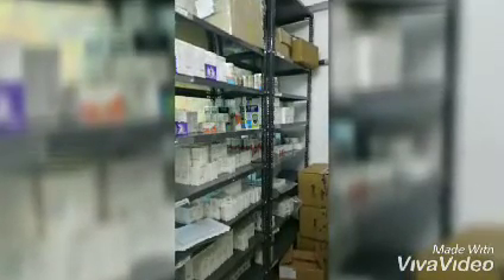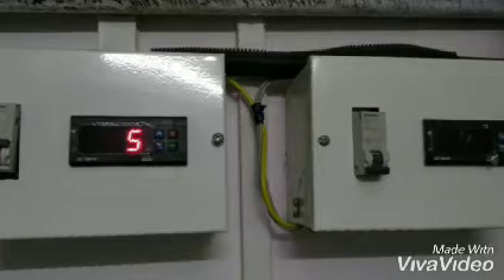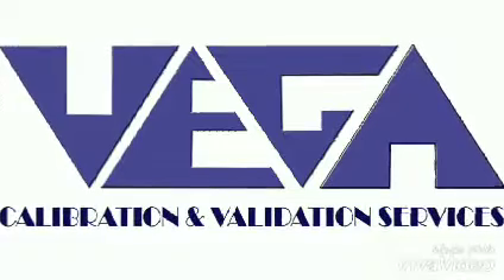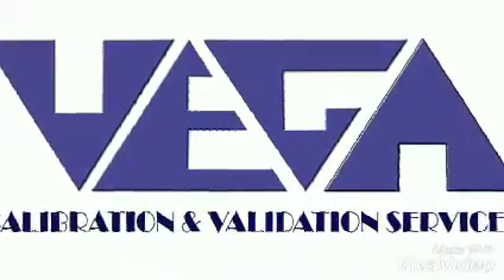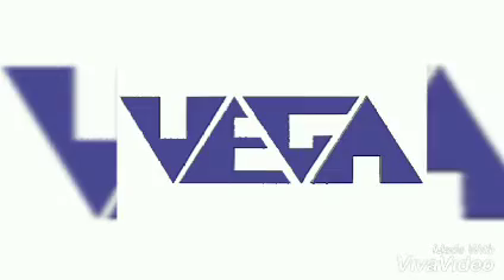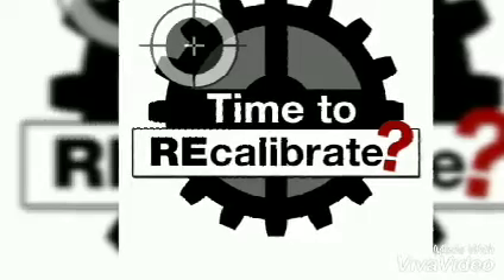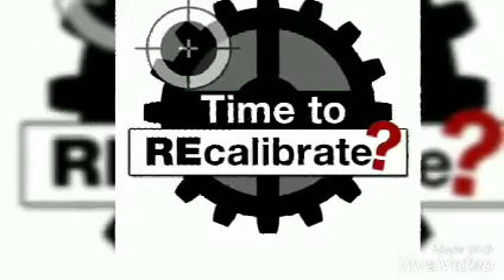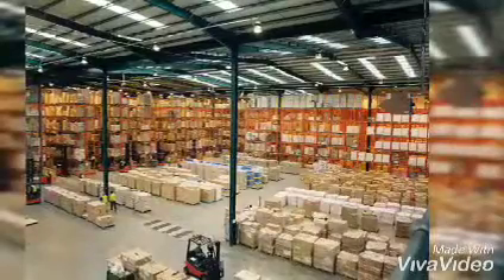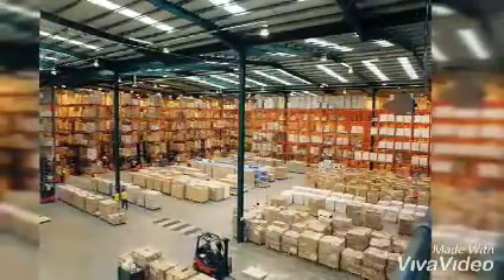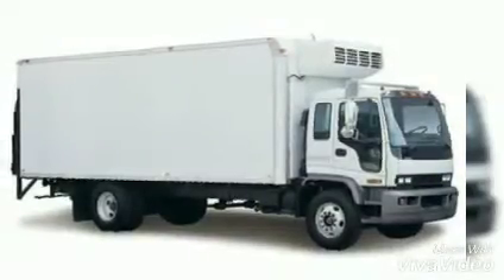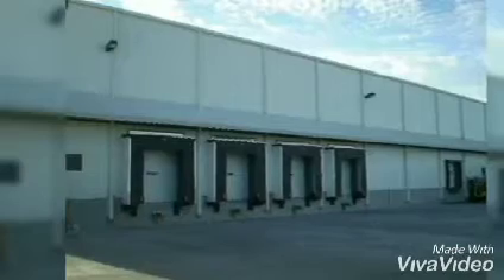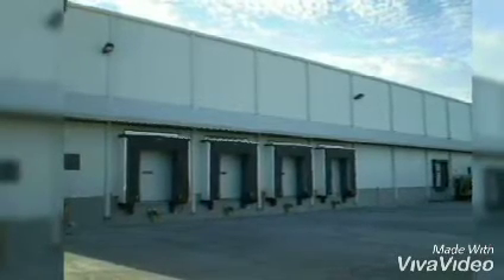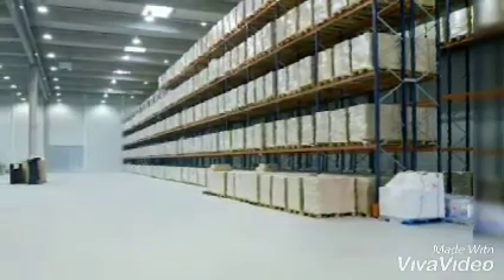So now, let us understand how VEGA performs the mapping study for its clients. The mapping study starts with a primary inspection of the area where the temperature mapping study is to be performed, and deciding the number of loggers and positions of the loggers. Once this is finalized, our VEGA engineers start with the mounting of the wireless temperature data loggers at the defined positions. Once the loggers are mounted, we start with the operational qualification study. This continuous cycle test study is to be carried out for 24 hours, 3 days or 7 days depending upon the client protocol. The operational qualification study cycle is also known as the empty cycle because the temperature mapping study is performed in an empty storage area.